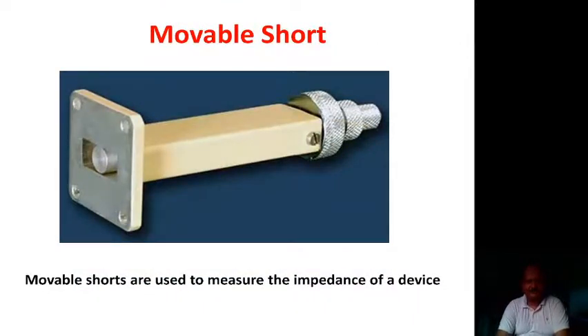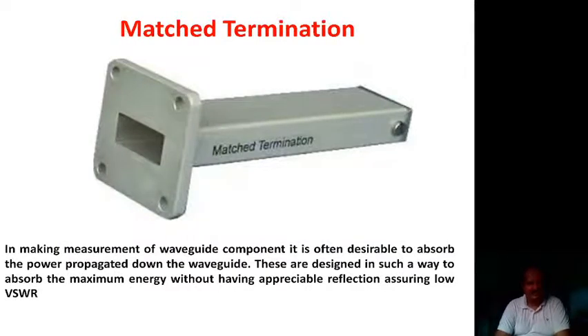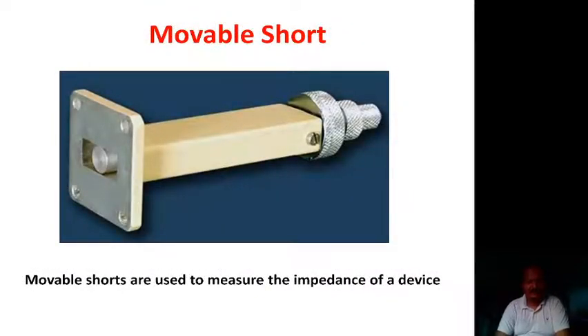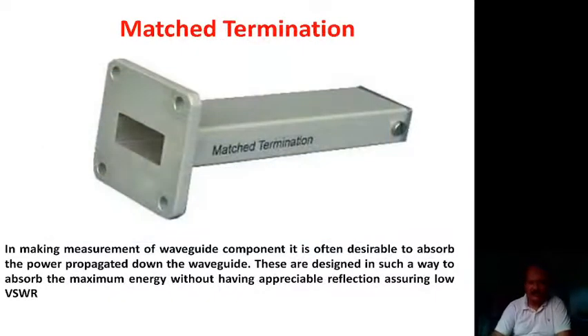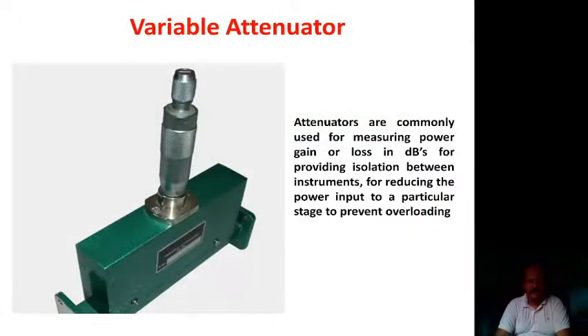Movable short is used to measure the impedance of a device. The match termination and a movable short look the same, but there is a small difference if you look at the right side. Movable short is to measure the impedance of a device; match termination is to absorb the power propagated down the waveguide. Variable attenuator is commonly used for measuring the gain or loss in dBs, and providing isolation between the instruments.